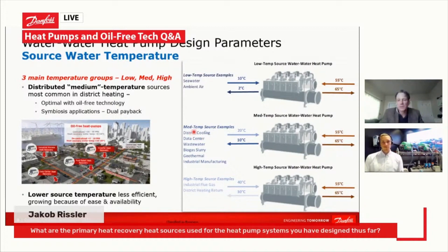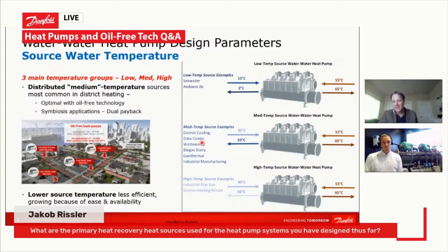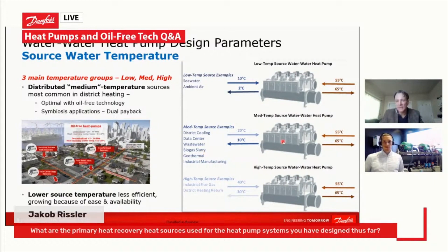For a district cooling application, you're reusing the district cooling return as the heat source. For a data center, you're cooling that data center and recovering the heat to, for example, a district heating system — or a proximity large heat load. Wastewater is actually, if you look historically in Europe and specifically at district energy systems, the most common application of heat recovery heat source for district heating. Biogas slurry is a related one where you're making use of the cooling to provide more efficient natural fertilizer back to the farmers of those biogas plants and then recovering the heat to the district heating.